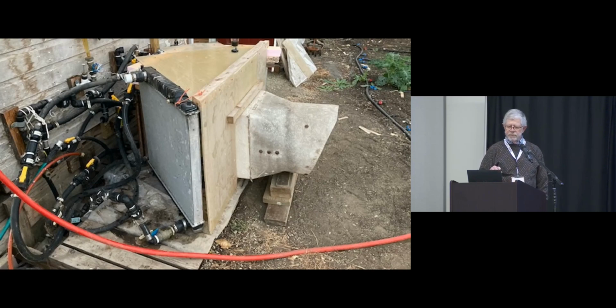We got smaller heat exchangers, but now added this third one in, this radiator, so there's more capacity to put heat away. But with the dryer loop being outside the footprint, there really wasn't a lot of point in putting heat back in the ground, since ambient heating and cooling controlled most of the temperature fluctuations there. I tried it for a while to see if I noticed a difference. I did not, so the temperature coming out of the ground is just a function of what Mother Nature makes it.